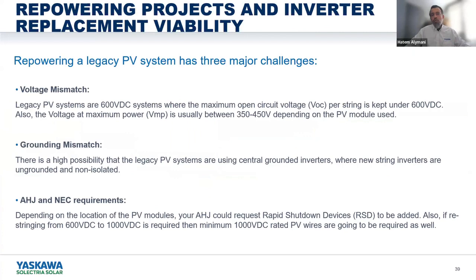The last thing I'm going to mention briefly is repowering. Whenever you see a repowering project, please tread carefully and contact us. This is actually an engineering project. It's not a simple swap, especially when you see 600-volt DC strings. 600-volt modules will create a lot of issues and a lot of challenges, mainly because you're not going to be able to meet that VMP for the inverter that we mentioned before. Your VMP per string is probably going to fall off, and it's going to be lower than the inverter VMP, and that will create unnecessary clipping and will reduce the overall production.